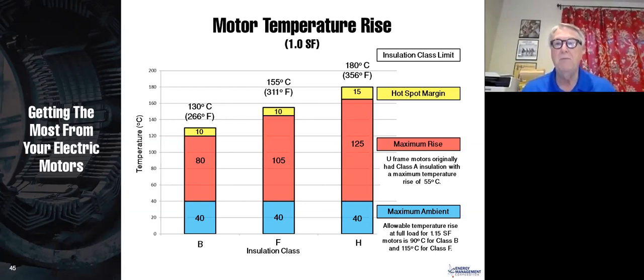Now a Class B motor was good for 80 degrees C rise, and that gave you a total temperature of 130 degrees C. As we mentioned, it's very, very common, and I highly, highly, highly recommend it to specify a motor that has Class F insulation but Class B rise. In other words, it's got the good insulation capable of 155 degrees C, but it will not run at more than 130 degrees C.